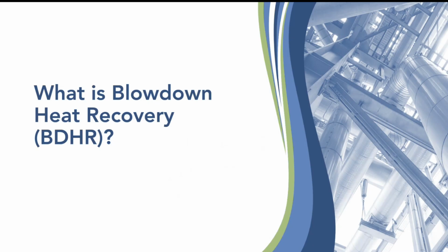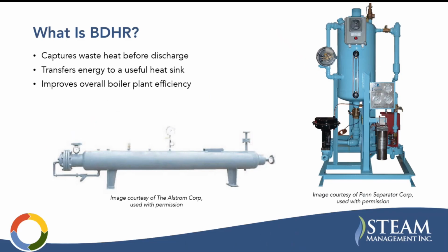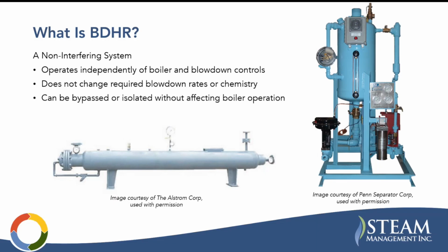All right, next section. What is blowdown heat recovery? We've kind of talked about it a little bit, but basically it captures that waste heat before it's discharged, transfers the energy to a useful heat sink, and provides overall boiler plant efficiency improvement. It should be noted this is a non-interfering system. So this operates downstream and independently of your boiler blowdown controls.